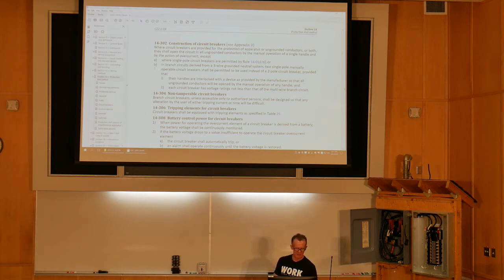Then B says, in branch circuits derived from a 3-wire grounded neutral system, 2 single pole manually operated circuit breakers shall be permitted to be used instead of a 2-pole circuit breaker, provided that their handles are interlocked with the device as provided by the manufacturer, so that all ungrounded conductors will be opened by manual means of any handle, and each circuit breaker has a voltage rating not less than that of the multi-wire branch circuit.